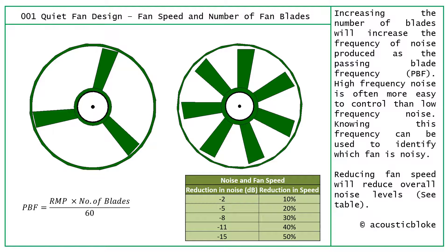We tend to find that if we add more blades and get a higher frequency noise from the fan, it's more readily controllable. It's easier to control higher frequency noise because it tends to be easier to absorb with acoustically absorbing materials, and it tends not to have such an impact over significantly large distances.